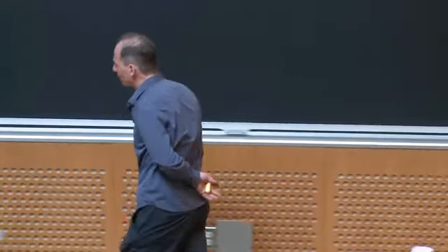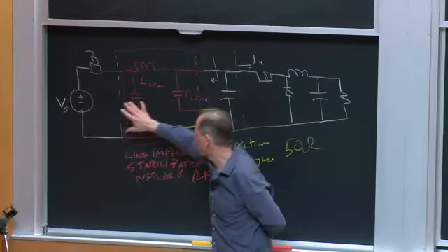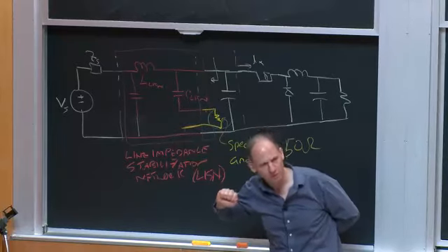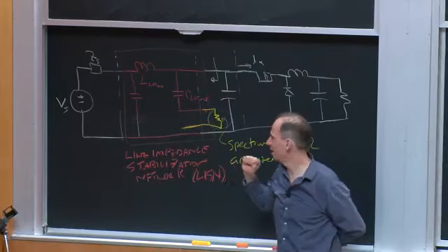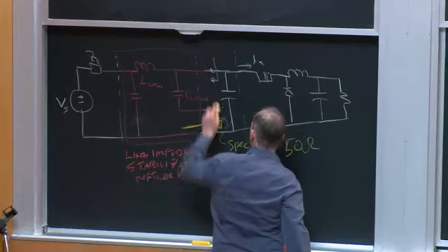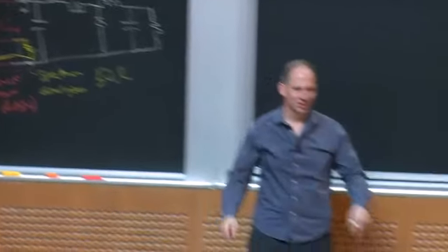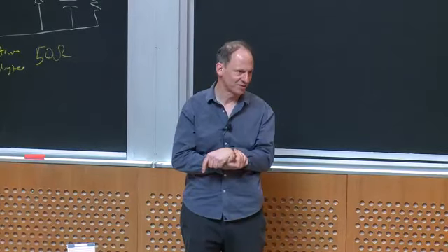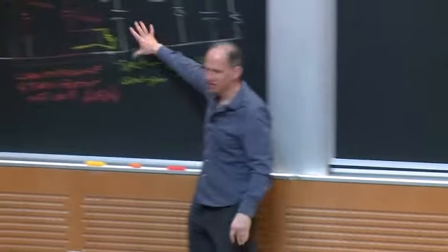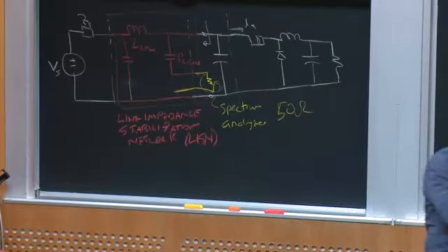I will say one other thing, by the way. I've drawn this as if you have a LISN that you stick in between your power source and your converter, and you do, but typically most specifications require that you put a LISN on this lead and a separate LISN on this lead, right? So there's actually 2 LISNs involved in a DC system test. We'll come back to why you would do that later, but the basic concept has not changed. It's the same idea, okay?